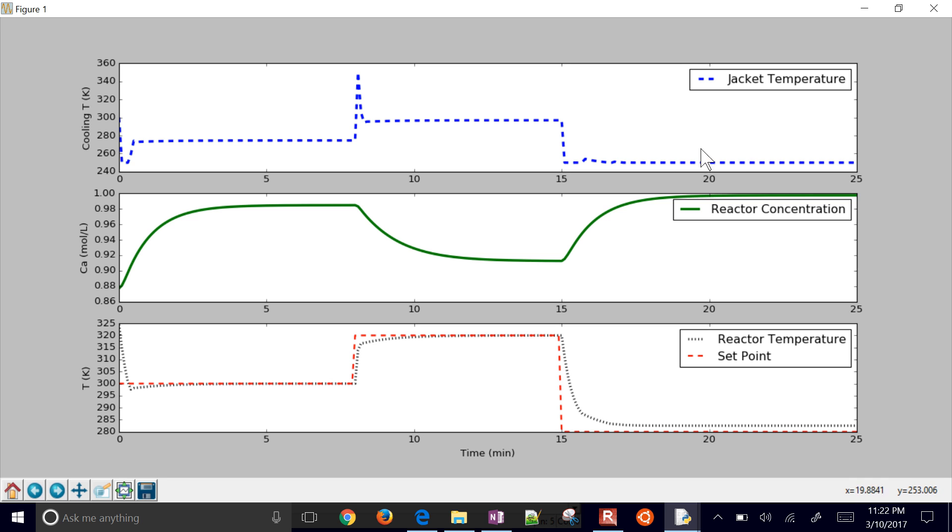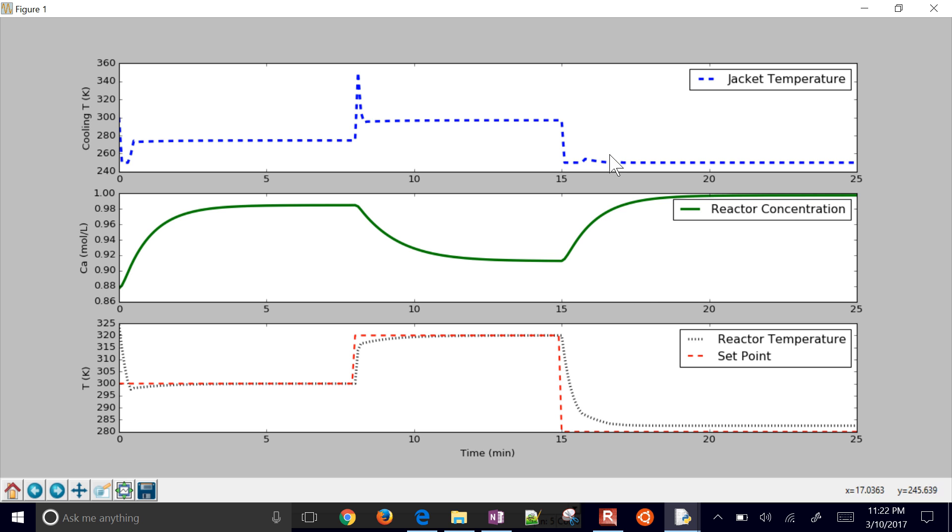You can see it doesn't ever quite reach the set point down here because this reaches a lower bound of 250. It can't go any lower. So the reactor actually can't go any lower than about 283 or so. That's the lowest that it can go because you can't get the jacket temperature lower than that.